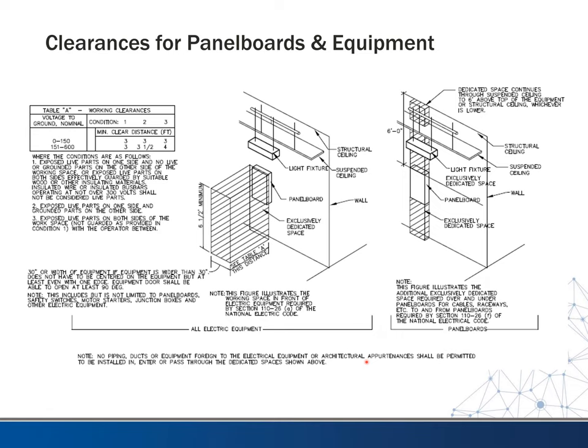So this is a common detail that I usually include on my plans that spells that out for people. And in front of panels, you're going to need at least 30 inches wide, and then you're going to need this clearance based on the table I just told you how far out. And then code also says that it has to be exclusively dedicated space below the panel and then clear to structure. So that means all the way to the roof deck. You can't run any piping through that area or any duct work or anything like that. So you just need to keep that in mind as you're coordinating your projects with other disciplines, that you have to have these dedicated spaces for electrical equipment and panel boards.